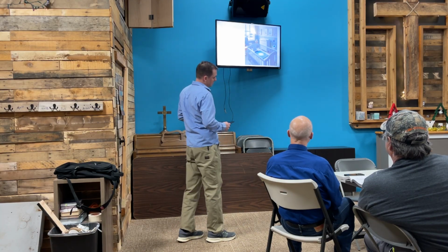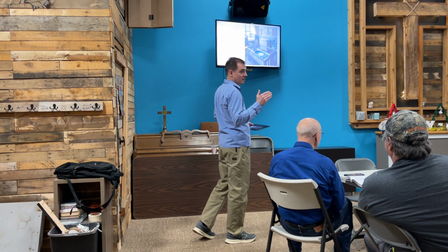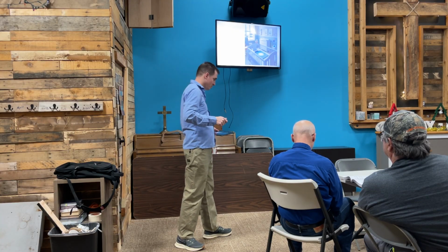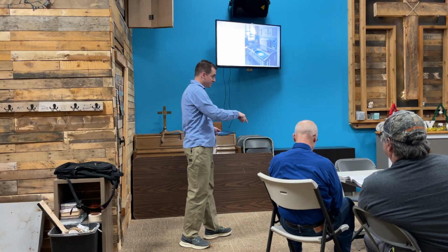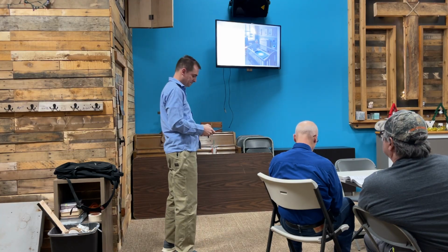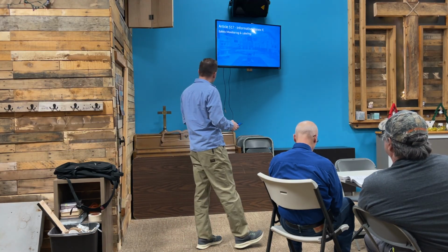I missed one other thing on this, I should have added. The last recommendation is to mark every other receptacle connected to the circuit that a life-saving machine is on. So when you go to plug something in, you'll be able to see this circuit is on the same circuit as a life support machine. I think that language is also in Annex K. There, warning, power loss risk. I meant to have that on there.